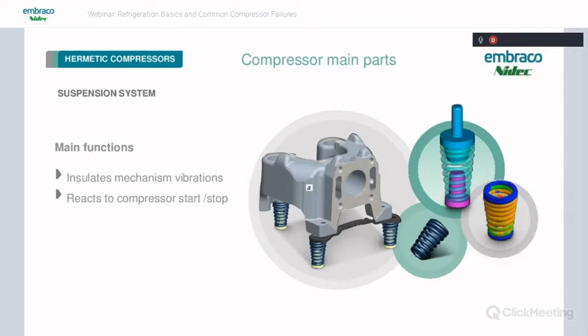If anyone's ever handled a hermetic compressor and you hear something knocking in there, that's the crankcase knocking against the inside of the compressor shell. Once it does that, you have exceeded the design limits of the suspension system. So if we ship a compressor like this in ground shipping, it can very easily damage it. The shocks and drops and tumbles of ground shipping can very easily damage this compressor, even if they're packed very well.